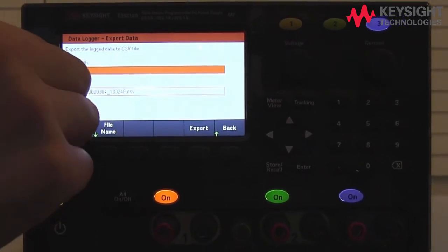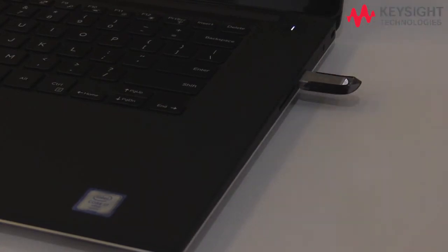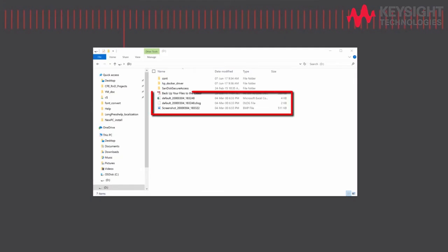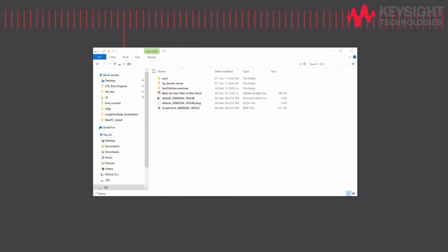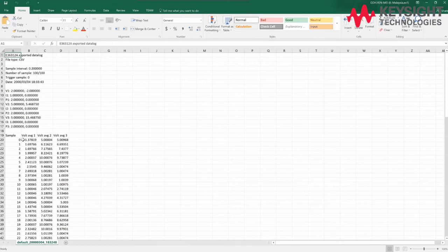Once data has been exported, pull out the USB stick and plug it into your PC. As you can see, there are three files in the USB drive: the screen capture, the DLOG binary file, and the CSV file which we exported earlier. Let's open the CSV file with Excel. You can see that data is logged in rows at every 200 milliseconds interval. Each column represents the different parameters captured in the data logging exercise. Further details and analysis can be carried out from here.